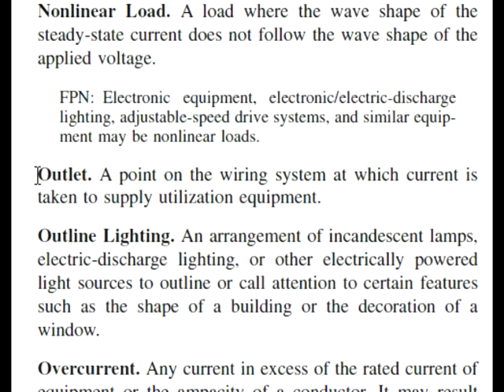Here we are at Article 100 in definitions. An outlet: a point on the wiring system at which current is taken to supply utilization equipment. So yes, your receptacle plug at home — that is an outlet. But a light switch, that's also an outlet — it's a switch outlet. The light itself is a lighting outlet. So keep that in mind; it's not just where you plug a receptacle into.